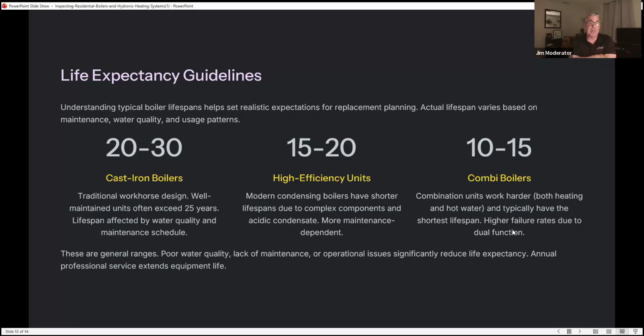But cast iron boilers, they last a long time. 20 to 30 years. I usually tell my clients 25 to 30 years. High efficiency units, I usually go 18 to 22 years. And combo boilers, they're saying 10 to 15 years. I think they're lasting longer. And again, these are general ranges, poor water quality, lack of maintenance.